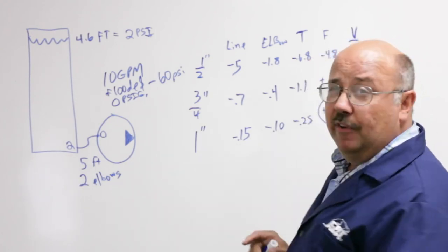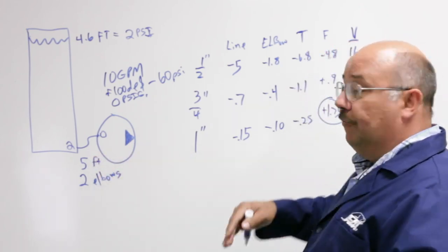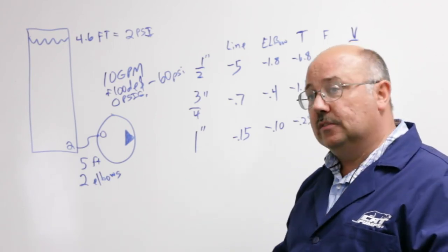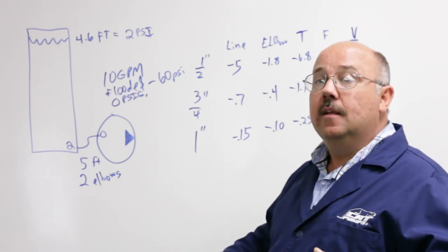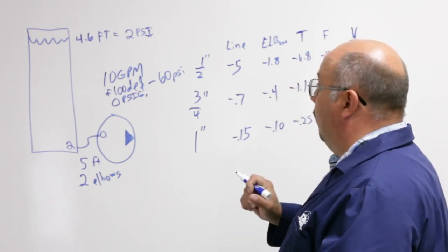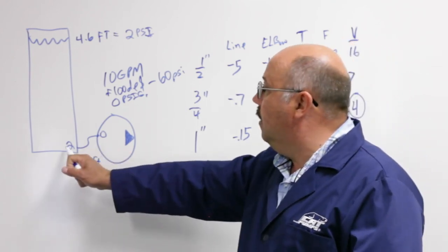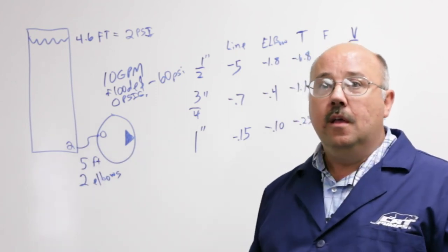And I would recommend doing both conditions, because even though you could have 4 feet per second in the inlet line, you could have too big of a drop if the line was really long, or you used many multiple elbows and twists and turns, which everything adds to the pressure drop in that line. So when you're sizing an inlet, it's very important to know your starting pressure and your line losses to make sure your inlet pressure on your pump is within the guidelines.